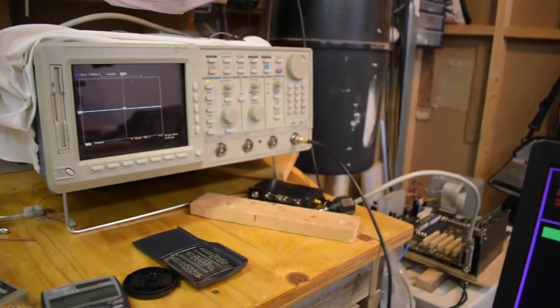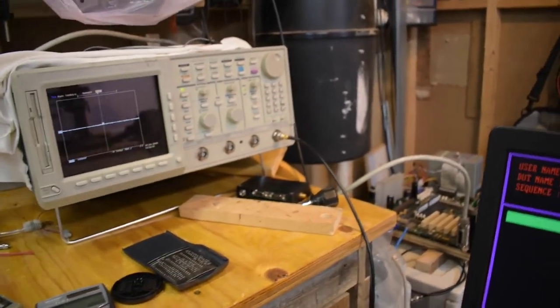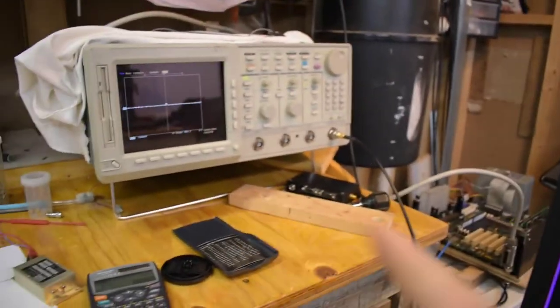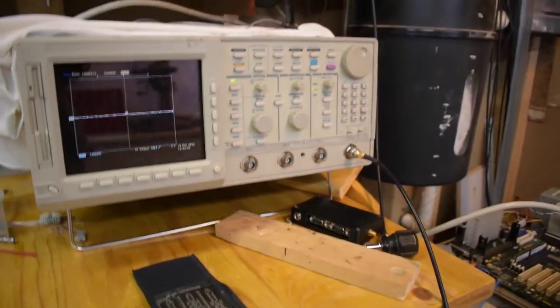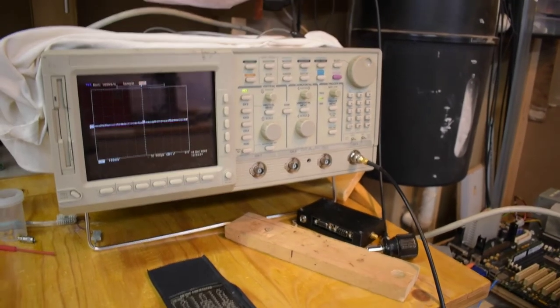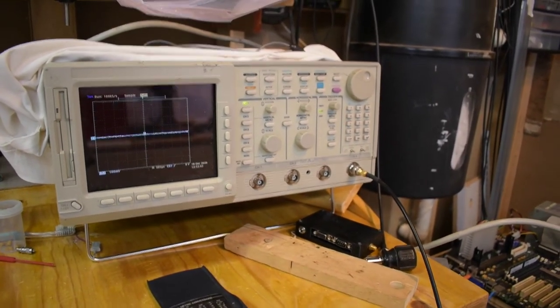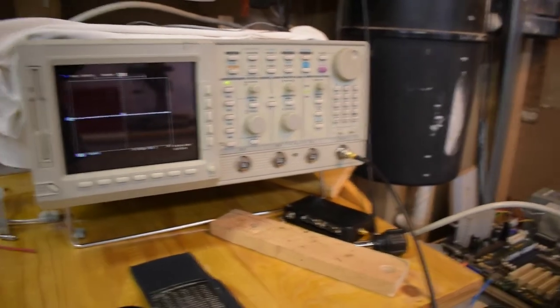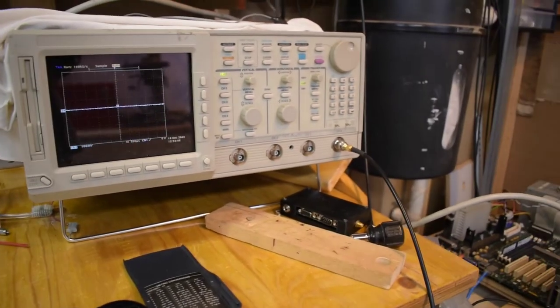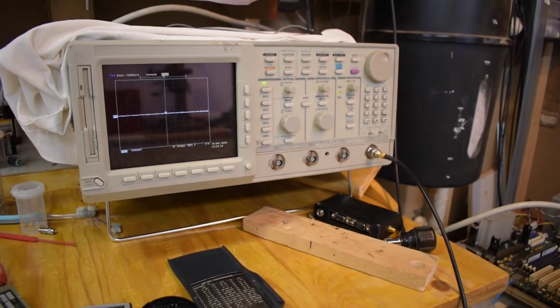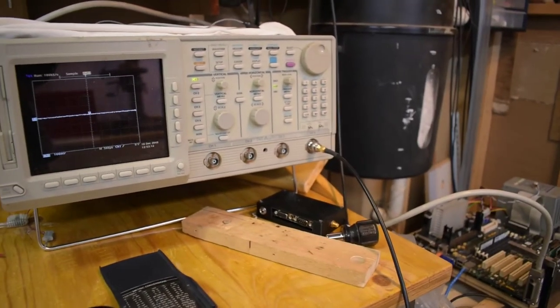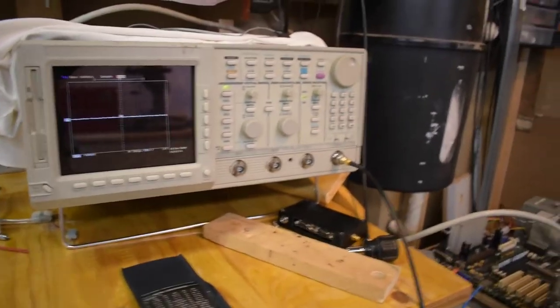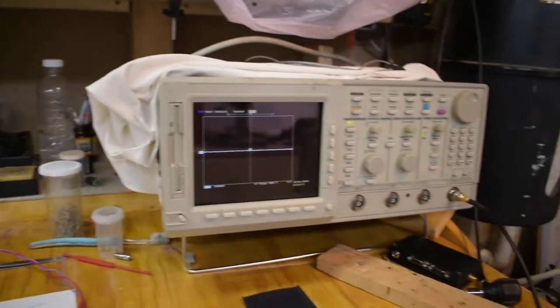Wow. I just finished the interleave. It went fairly well. It is pretty hands-on. It takes about 5 to 10 seconds every step, then you gotta change over the connections. And I think due to my sort of botched CVR cal from yesterday, the gain isn't quite the same on, I think, channel 1 or 2 is the worst. It's a few percent off, so I just had to tweak the amplitude now and then just to keep it inside those 6 divisions that it asked for.